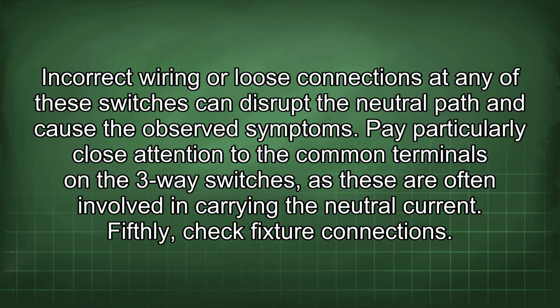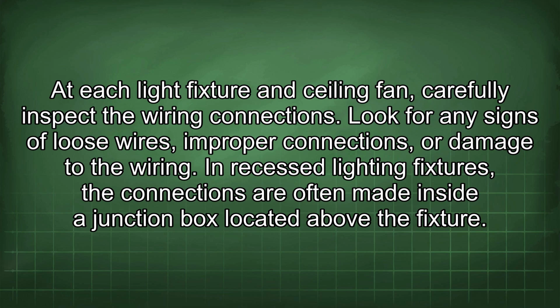Incorrect wiring or loose connections at any of these switches can disrupt the neutral path and cause the observed symptoms. Pay particularly close attention to the common terminals on the 3-way switches, as these are often involved in carrying the neutral current. Fifthly, check fixture connections. At each light fixture and ceiling fan, carefully inspect the wiring connections. Look for any signs of loose wires, improper connections, or damage to the wiring.